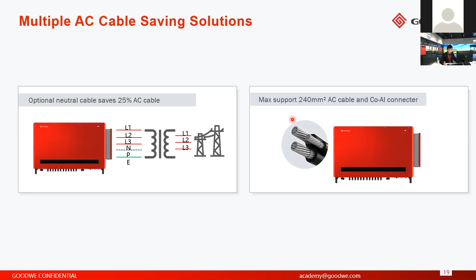And here is the HT series, here is the AC connection box. For the AC connection box, the maximum we can support is 240 square millimeters AC cable. So that means you can use aluminum cable to connect to the HT series, and the aluminum cable is much cheaper than copper cable. So if you use aluminum cable, that can also save the AC cable cost. But the aluminum cable size will be much bigger than copper cable. So that's why we design the AC connector so big.